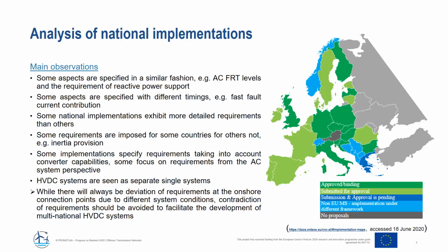What's common for all these national implementations is that the HVDC systems are seen as separate single systems. So there's also no specification on an overall DC grid code here. And what's in general to be stated is, while there will always be a deviation of requirements at the onshore connection points due to the different system conditions, contradiction of requirements should be avoided to facilitate the development of multinational HVDC systems. And this is even more important when we look at the development of a multi-terminal system offshore, where it really has to be ensured that the requirements from the different national grid codes do not impede the connection of the different systems in the future.